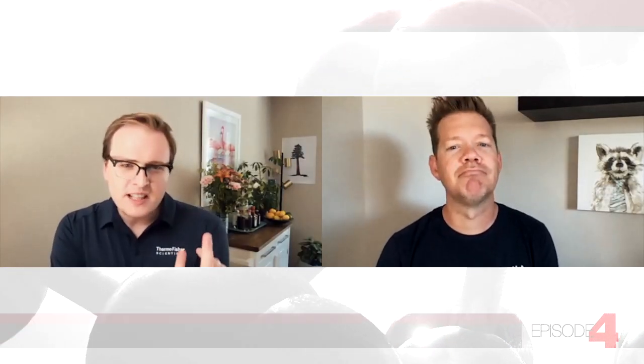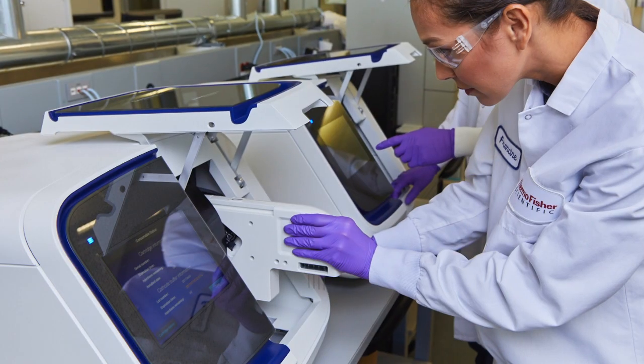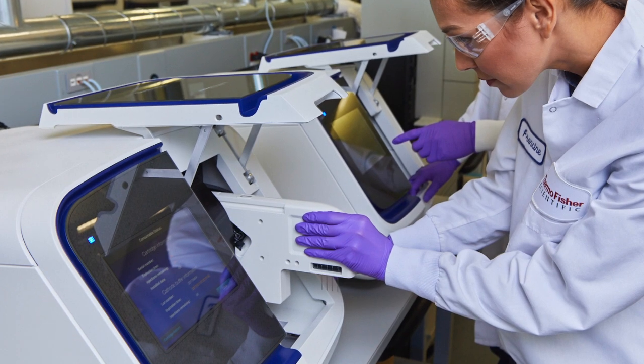Well, we've got the capillary array, the polymer, the polymer delivery system or pump, the anode buffer container — all in a single unit tracked with RFID. And it's so easy to install. You just slide that cartridge in and it spatially calibrates itself.